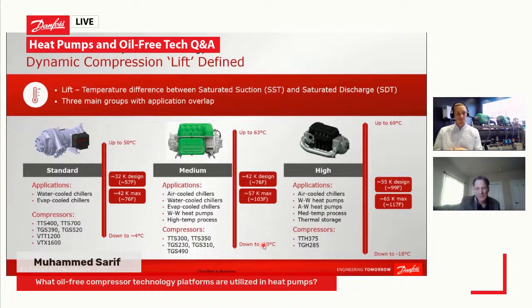And for a heat pump, and to Mohammed's question, for a heat pump application, it really depends on the system design. And I'll show architecture examples later. But we've seen that depending on the heat pump system application, it's almost never one. We have three main optimizations of the compressor designs: a standard lift, which is used for water-cooled chillers primarily; a medium lift, which is kind of a hybrid for water-cooled chillers, less challenging air-cooled chillers, and then less challenging water-to-water heat pump applications, or low-stage water-to-water heat pump applications; and then the high lift, which enables the highest operating maximum temperature point and the highest differential temperature, so from the low side to the high side.